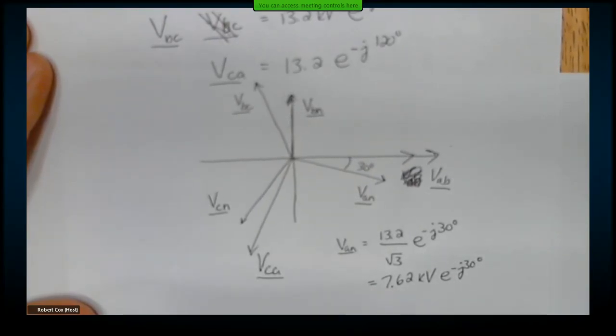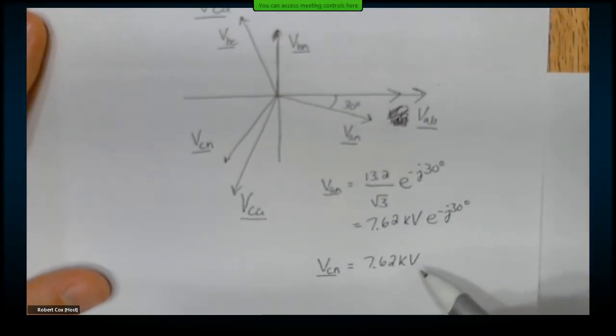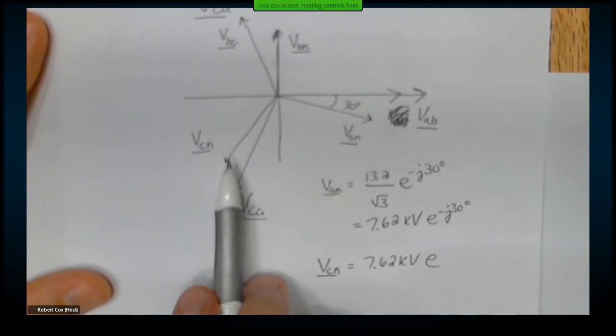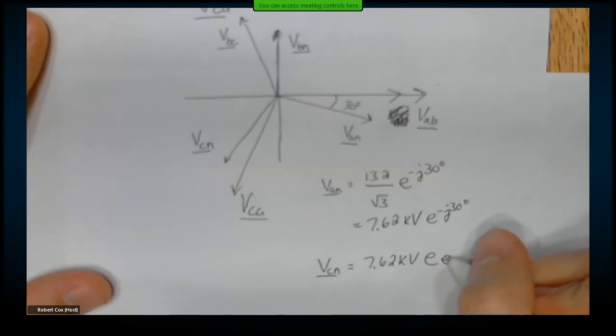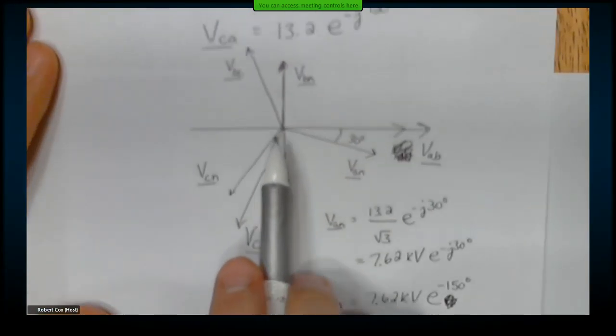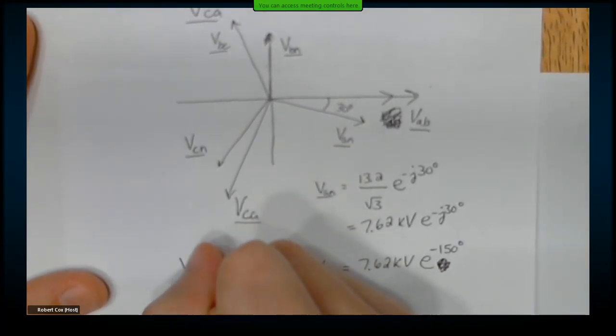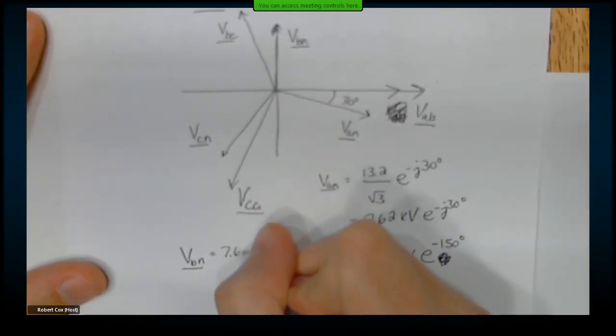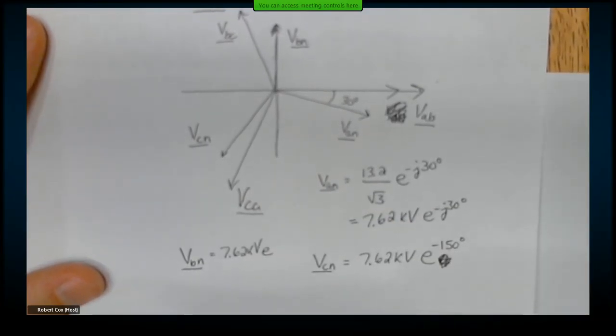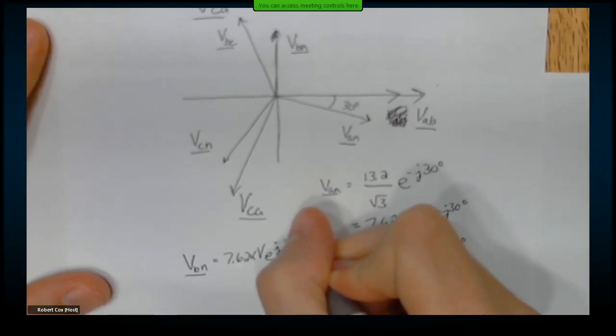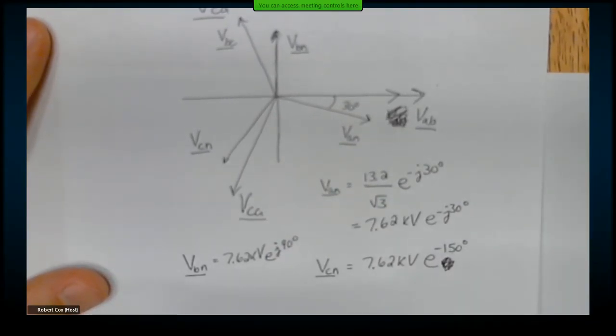According to this, VCN is at 13.2 — same magnitude, 7.62 kV. He looks like he's 30 degrees behind this guy, so that puts him at negative 150 degrees. If VCA was minus 120, that puts him at minus 150, which is 30 degrees behind. VBN, on the other hand, has the same magnitude, 7.62 kV. He's 30 degrees behind this guy, so that puts him at 90 degrees. So my VAN is that.